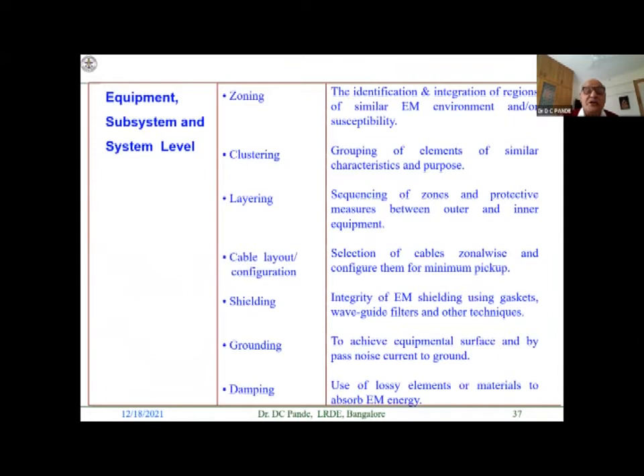We do the zoning, electromagnetic zoning, clustering of the system, layering. Then we do the different cable layout, their configuration, impedance control, different types of shielding. A super screen cable's transfer impedance is to be minimum 0.001 milliohm per meter. Then shielding has to be done. Shielding integrity is maintained by gaskets, finger shapes, and honeycomb filters.